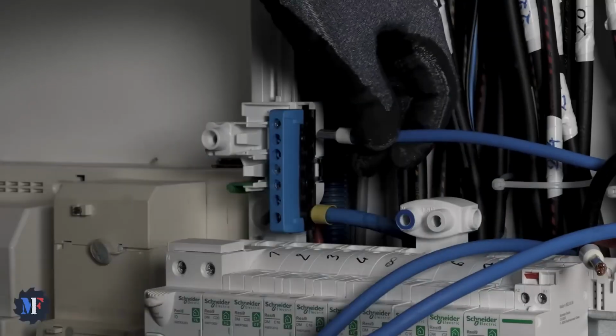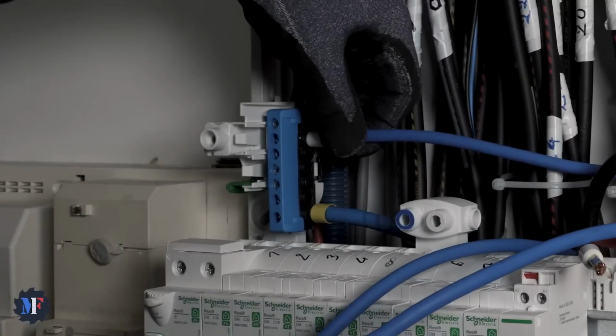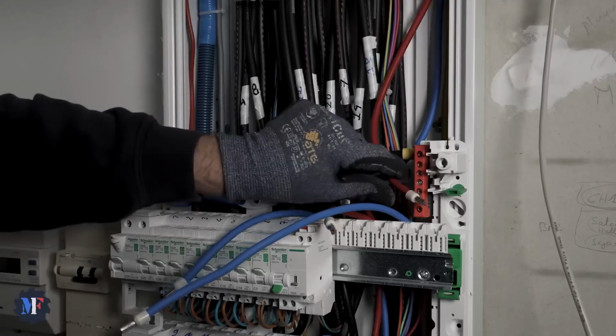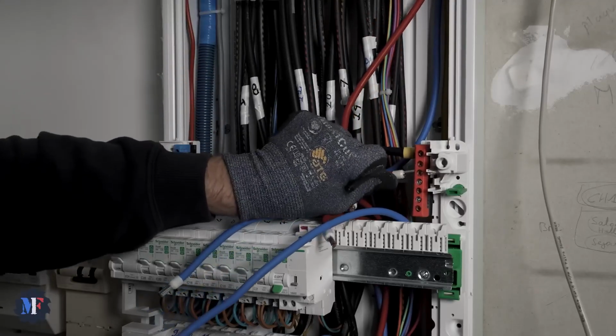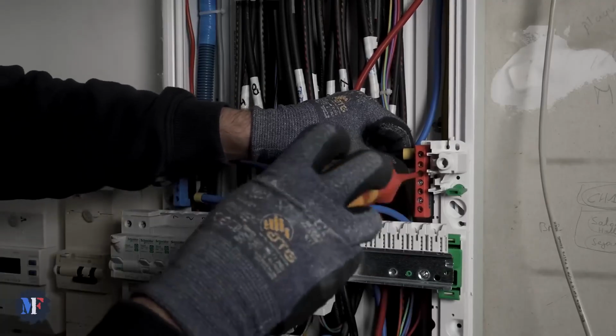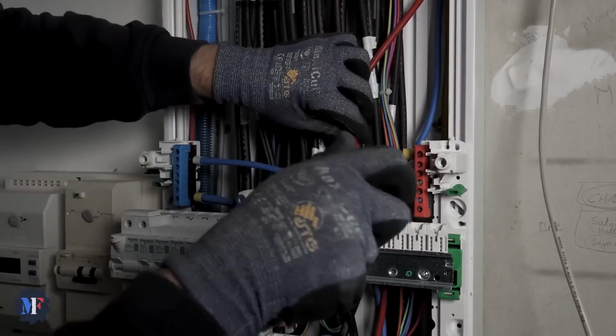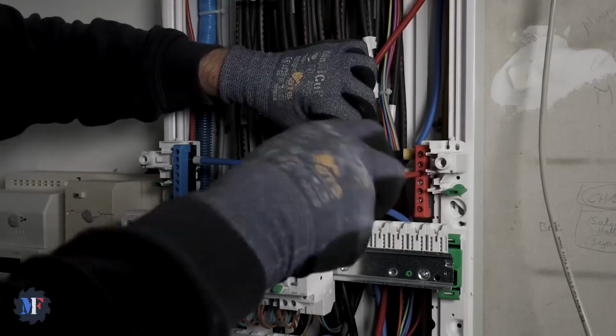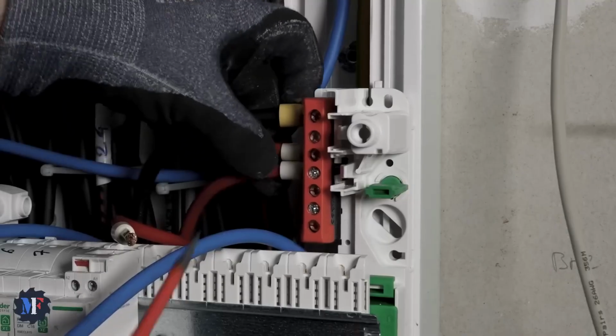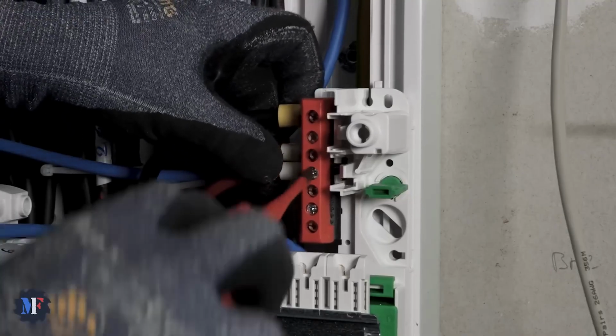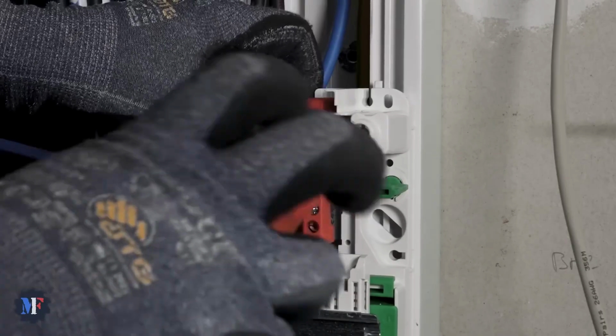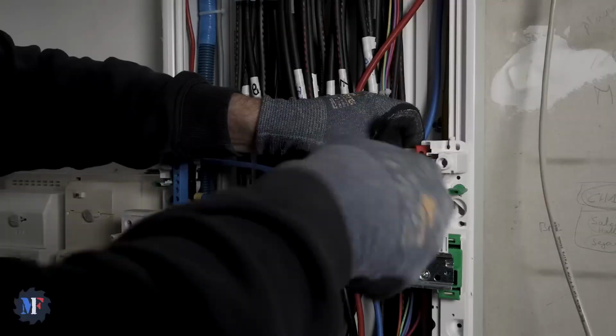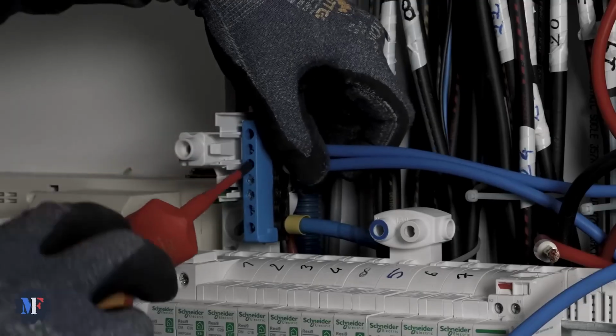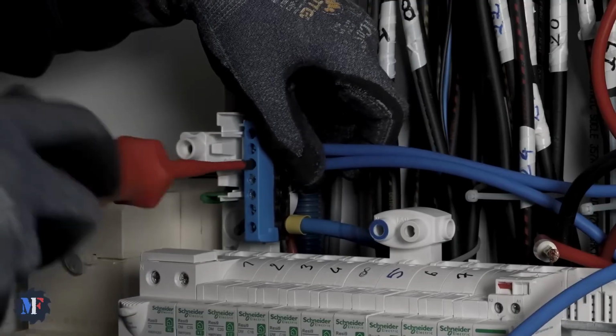So the secondary panel, there we go, we're going to put it here. The phase wire, we're going to run it underneath. So this is the phase wire from the secondary panel that's upstairs. This is the residual current circuit breaker I installed on the module of 5, just like I did for the secondary panel. I'll film that for you again in a little while.